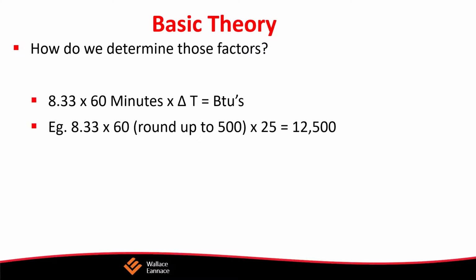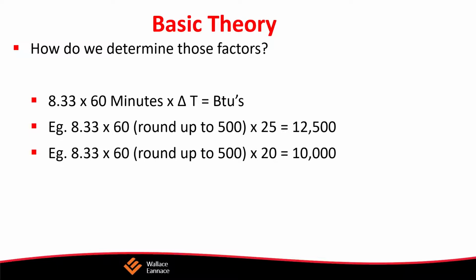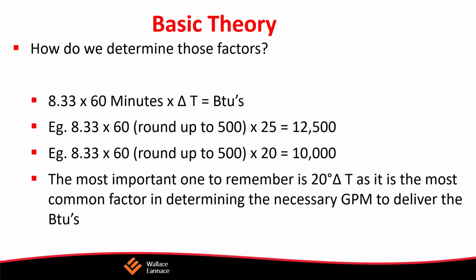How do we determine these factors? Once again, 8.33 times 60 minutes times delta T gives me the BTUs. 8.33 times 60, rounded up to 500, times 25 gives me 12.5. 8.33 times 60, rounded up to 500, times 20 gives me 10,000. The most important thing to remember is that 20 degrees delta T is the most common factor in determining the necessary GPM to deliver BTUs.